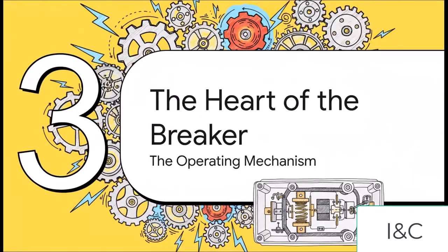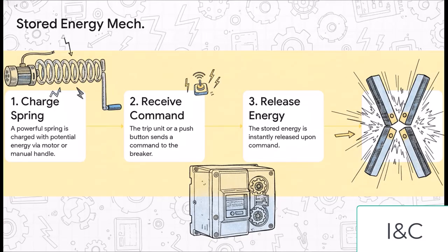Okay, so we've seen the controls on the outside, but where does the incredible raw force to open and close that circuit actually come from? Let's go under the hood and look at the real heart of the breaker, the operating mechanism. It all comes down to this, the stored energy mechanism. This is the muscle. So first, a massive spring gets wound up, charged with a ton of potential energy. Think of winding up a giant, powerful clock. That's done by the motor, or that manual handle we just saw. Then, the second the trip unit gives the command, all of that stored energy is released in a flash. This unleashes this immense force that is needed to slam the electrical contacts open or closed with unbelievable speed.